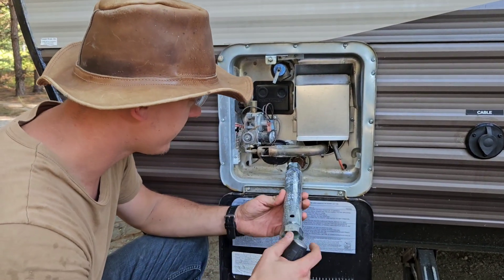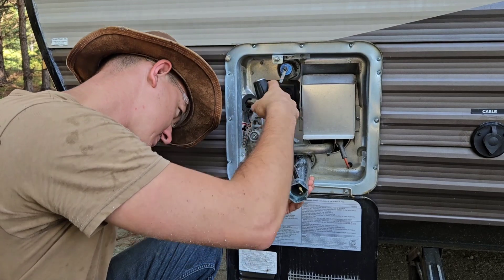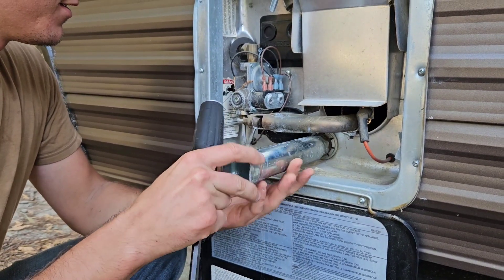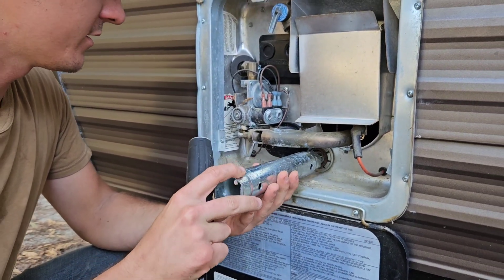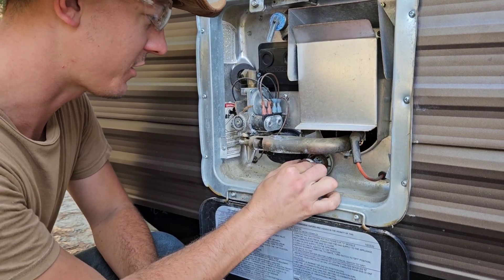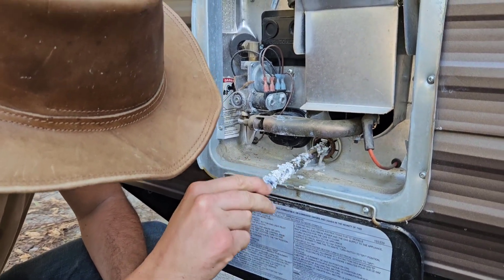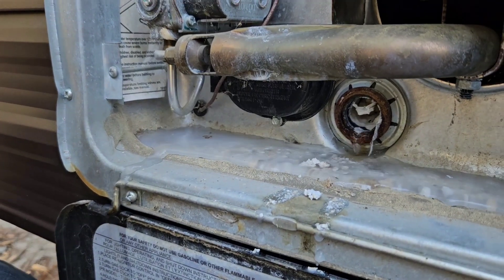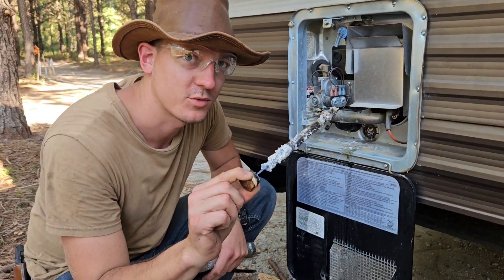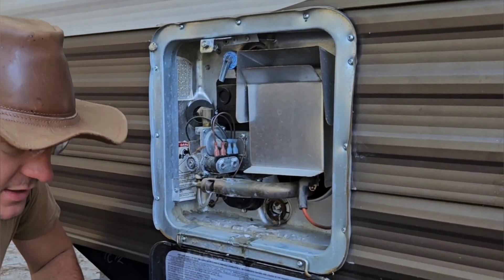I'm ready to remove the anode rod. I've got my anode rod removal tool. Let's see how bad this thing looks — it's probably never been replaced before. Oh my gosh, there's not even an anode left and it's all completely clogged up in there. The tank is very calcified in there. This is why you replace it once a year — because this tank is very, very calcified. The tank needs to be cleaned out now.